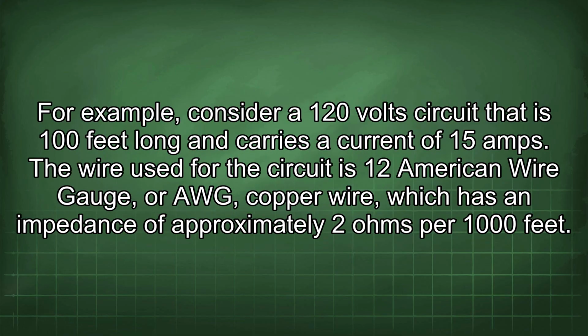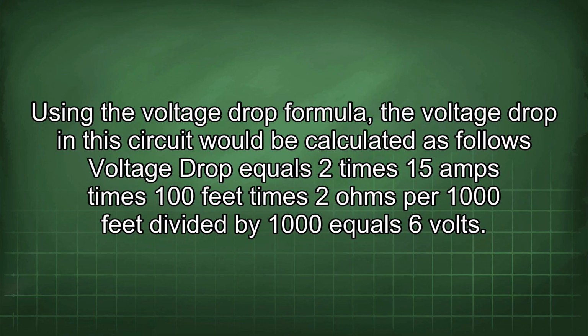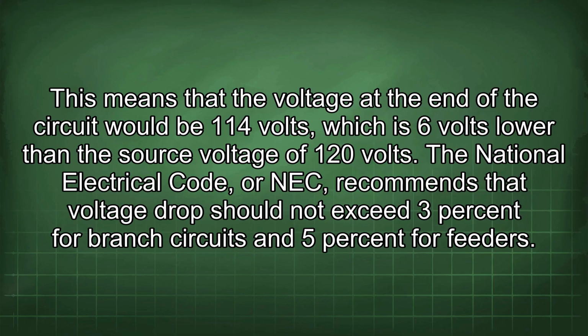For example, consider a 120-volt circuit that is 100 feet long and carries a current of 15 amps. The wire used for the circuit is 12 American wire gauge, or AWG, copper wire, which has an impedance of approximately 2 ohms per 1000 feet. Using the voltage drop formula, the voltage drop in this circuit would be calculated as follows: voltage drop equals 2 times 15 amps times 100 feet times 2 ohms per 1000 feet divided by 1000 equals 6 volts. This means that the voltage at the end of the circuit would be 114 volts, which is 6 volts lower than the source voltage of 120 volts.